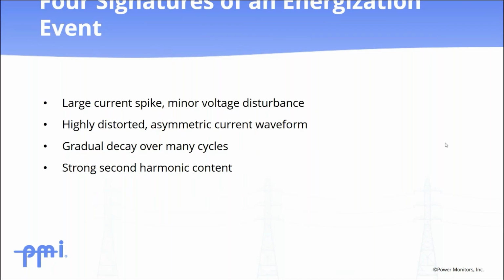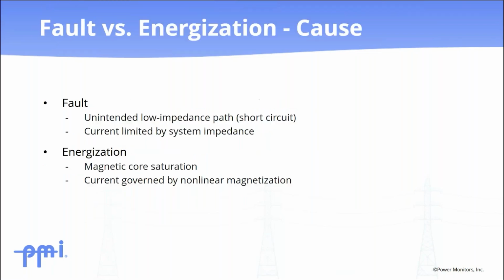A gradual decay. The transient current is large for several cycles and then steadily decreases as the magnetizing flux stabilizes. It tapers off and it doesn't snap off. And a strong second harmonic current. The harmonic analysis on an inrush current will show a significant second harmonic, which is a very characteristic fingerprint of magnetizing inrush, and it's actually what protection engineers use to keep transformer differential relays from tripping during energization. This is the part that really matters for day-to-day PQ work.